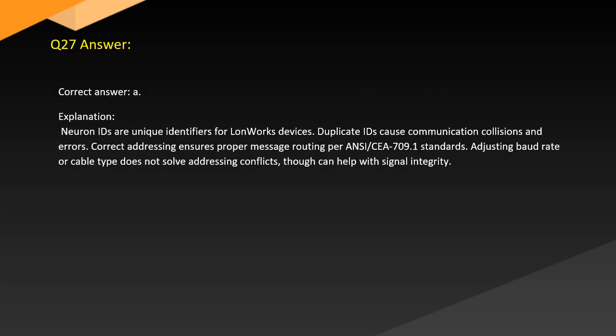Answer. Correct answer: A. Explanation. Neuron IDs are unique identifiers for LonWorks devices. Duplicate IDs cause communication collisions and errors. Correct addressing ensures proper message routing per ANSI 709.1 standards. Adjusting baud rate or cable type does not solve addressing conflicts, though it can help with signal integrity.